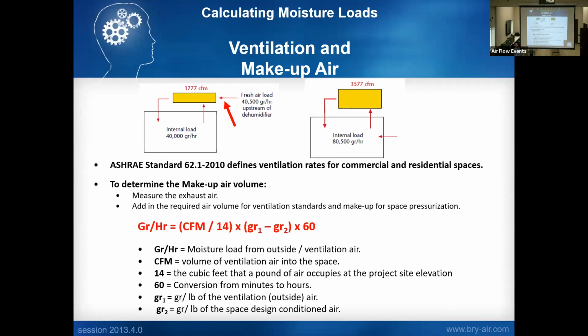So typically, you know, we do fresh air a couple different ways. One, we bring it right into the dehumidifier through the makeup air. Or it's brought in through, again, the other source, but we have to have the CFM to overcome that additional load.